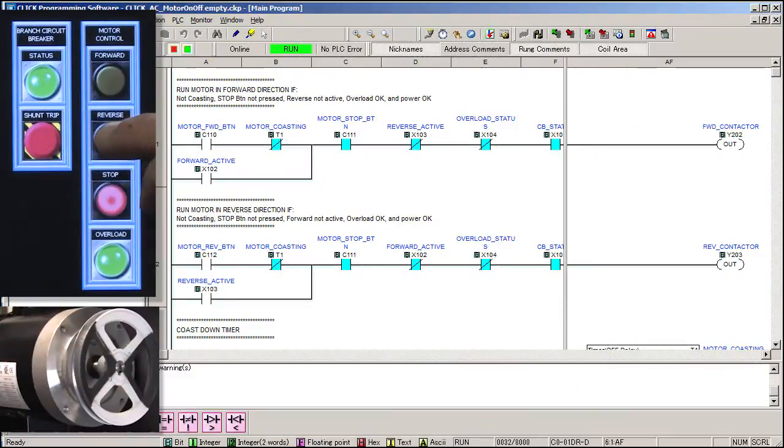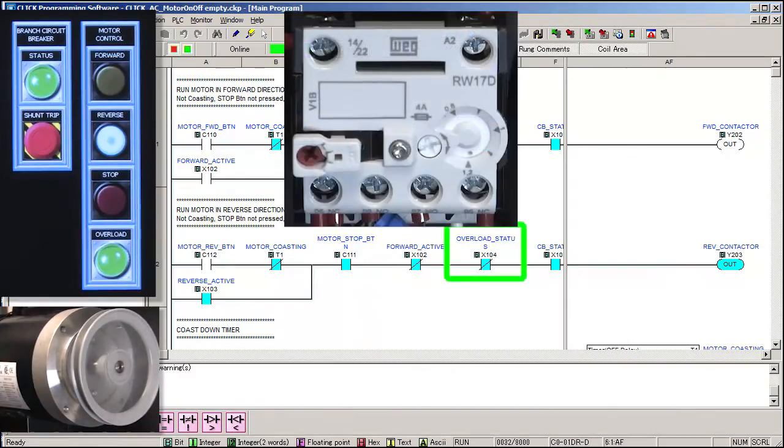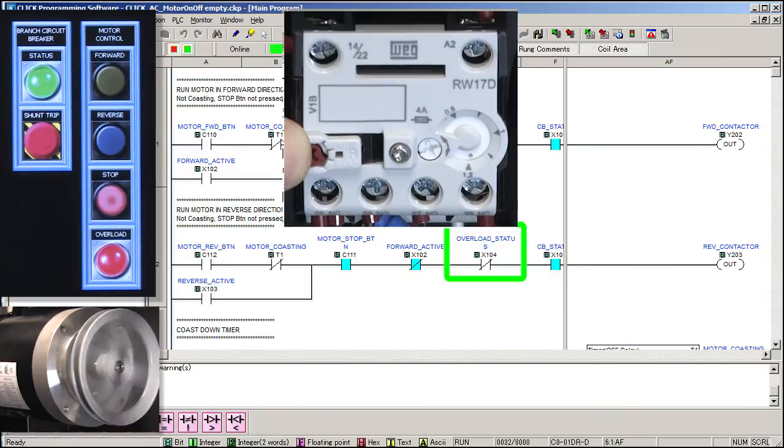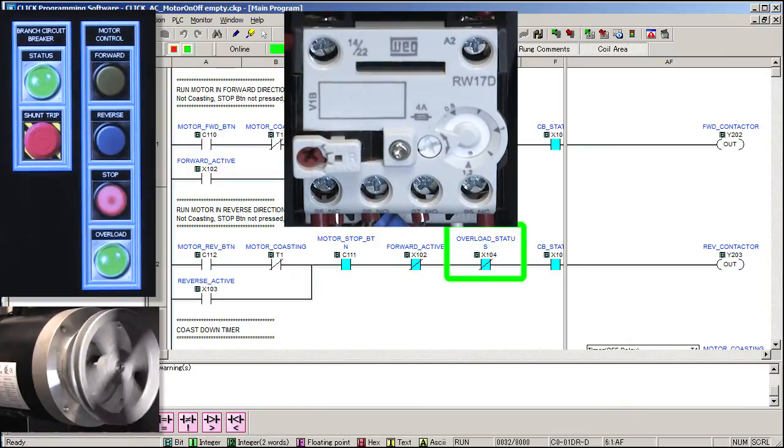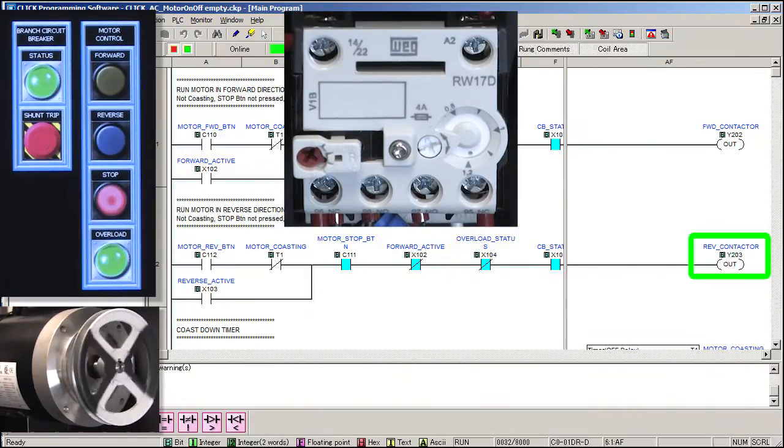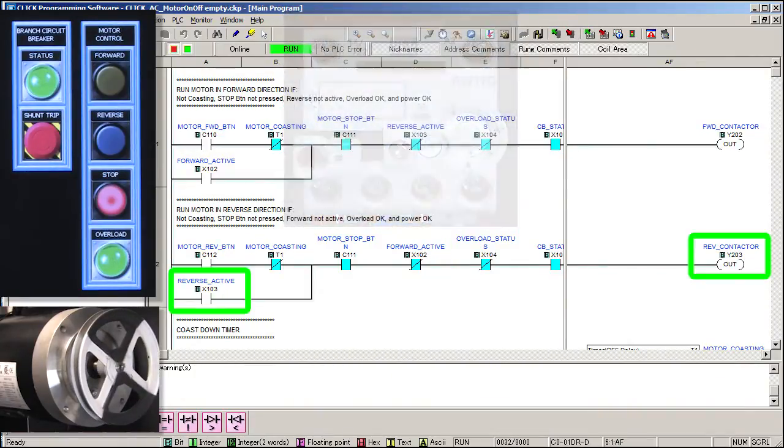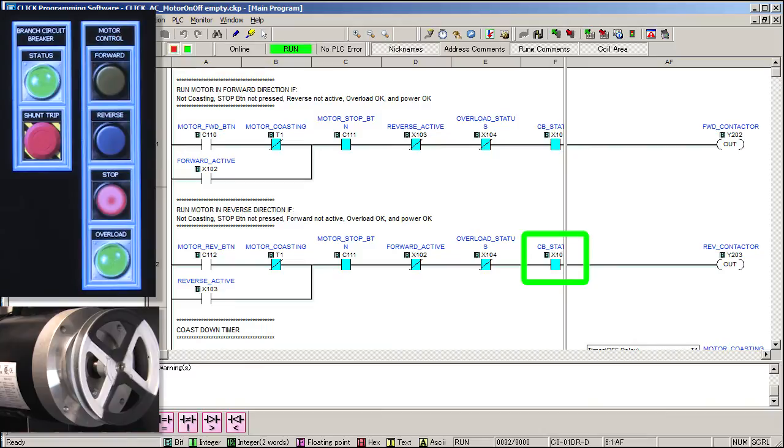Let's start the reverse direction, which works exactly the same as the forward circuit, but this time we'll press the overload test button and sure enough, it deactivates this contact which disables the contactor and its AUX contact which kills the power to the motor. Exactly what we expected. The circuit breaker AUX contact would work the same way.